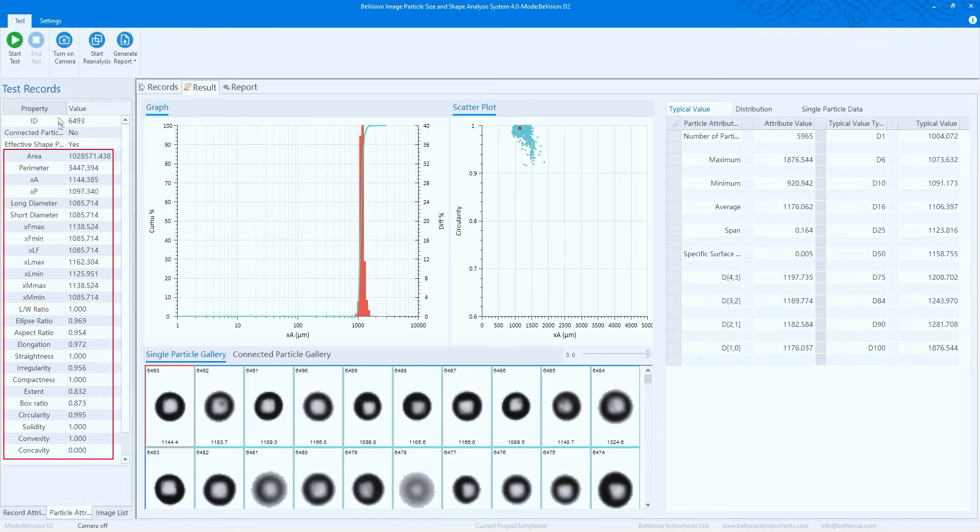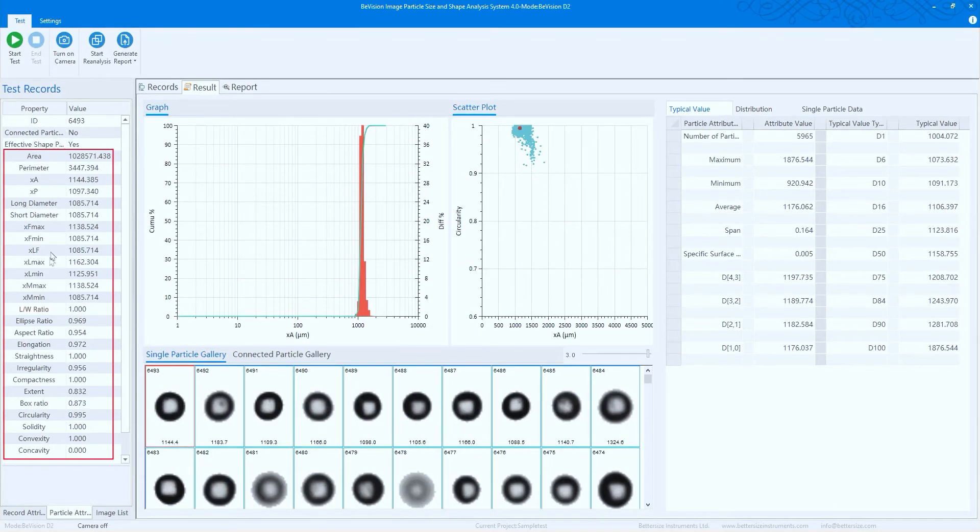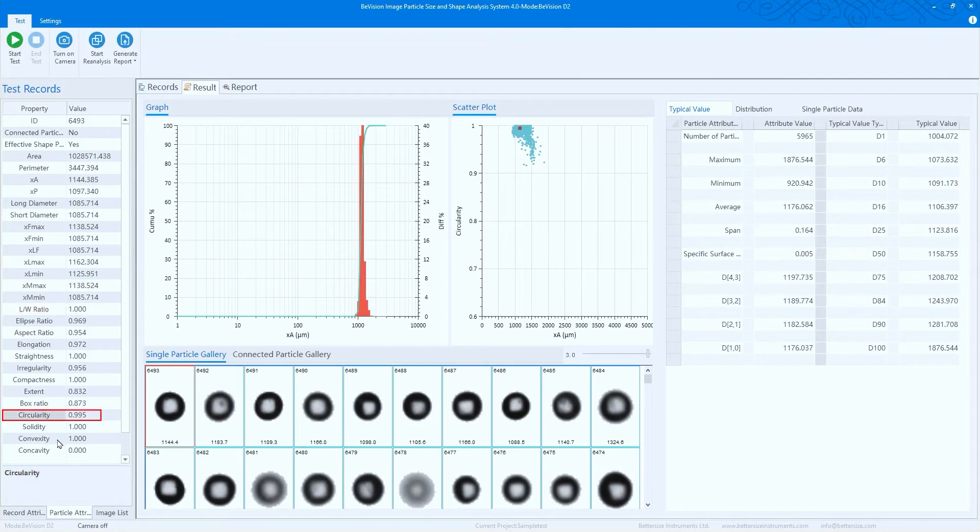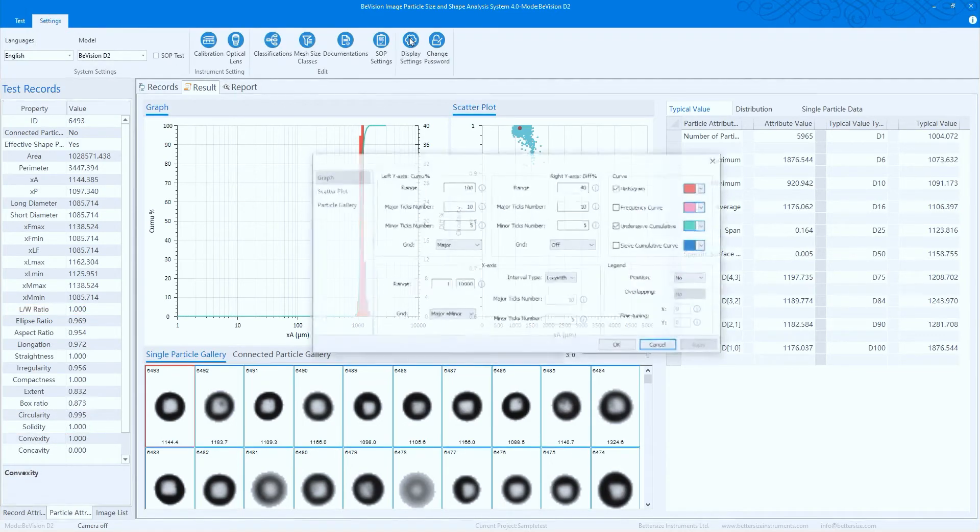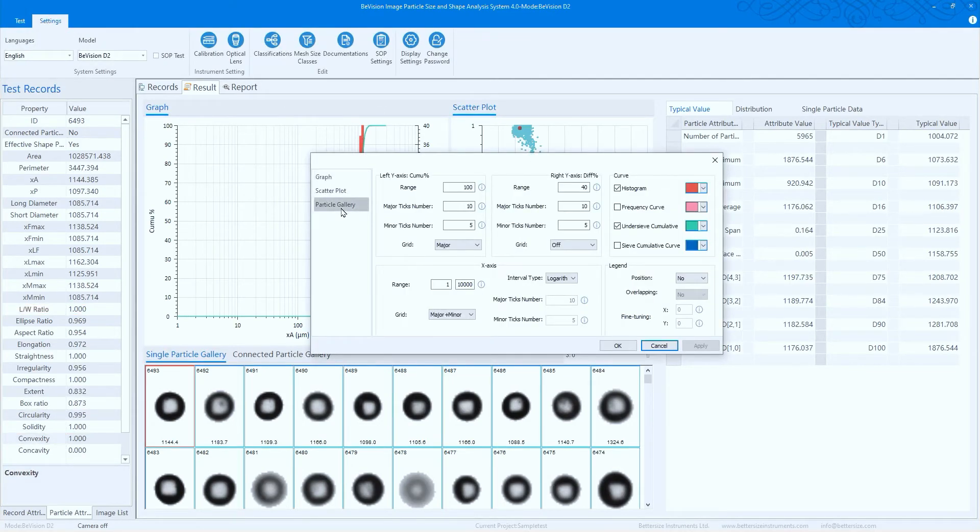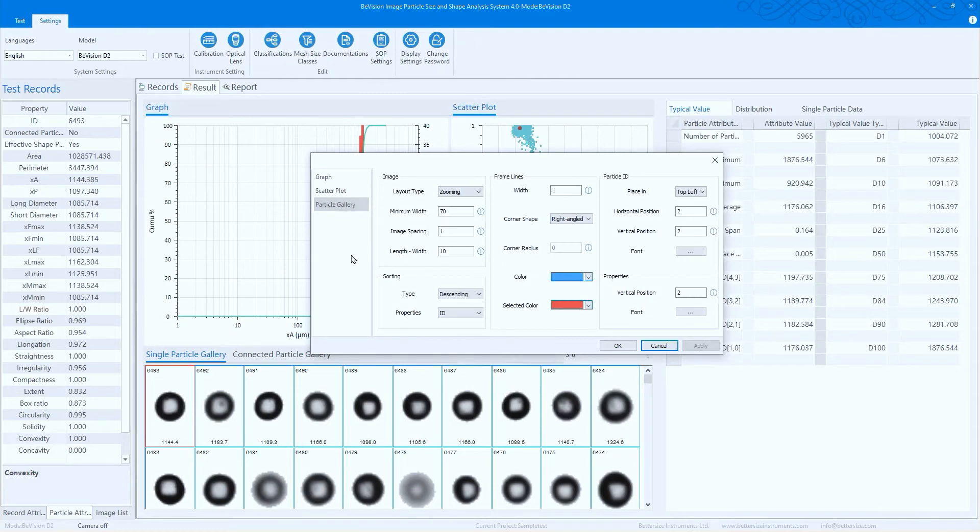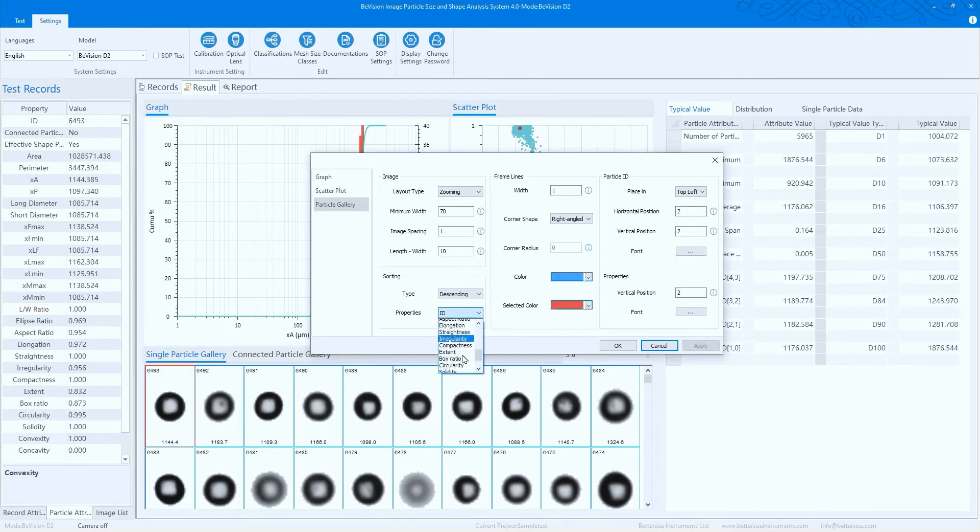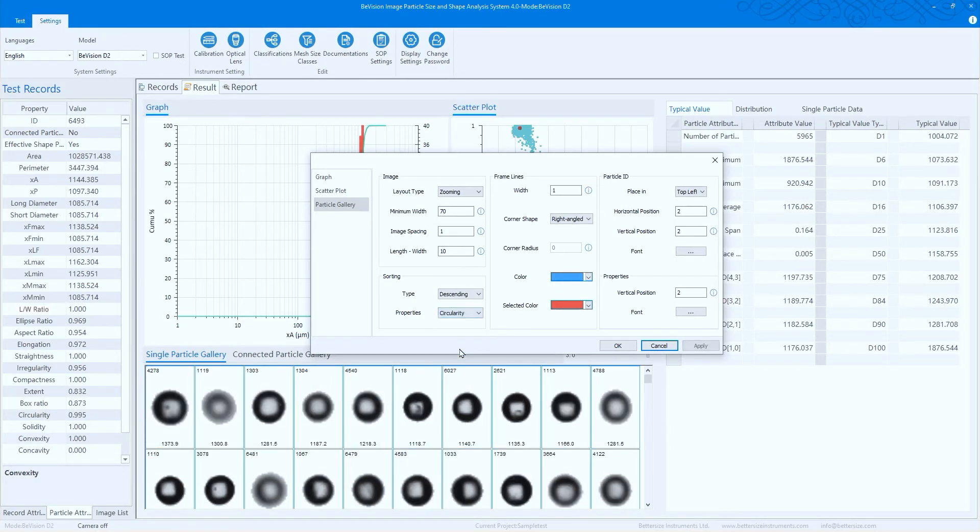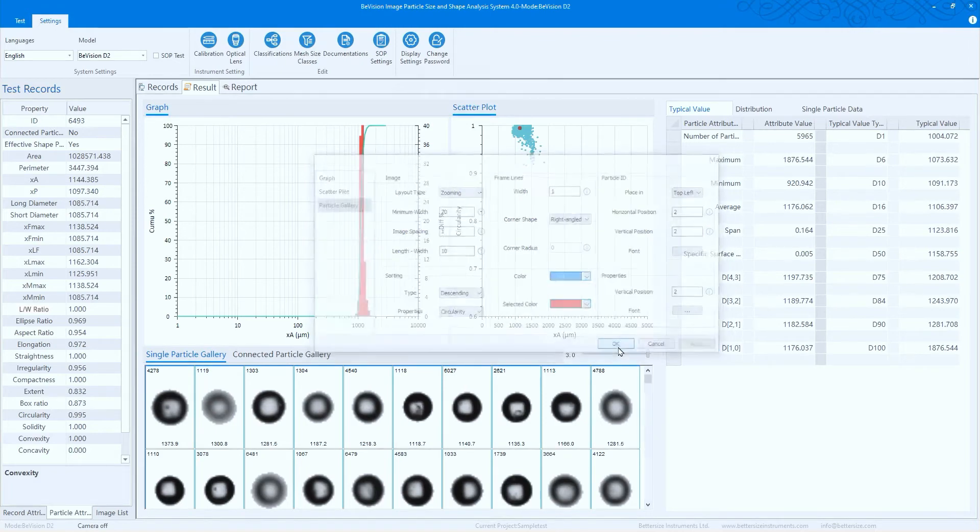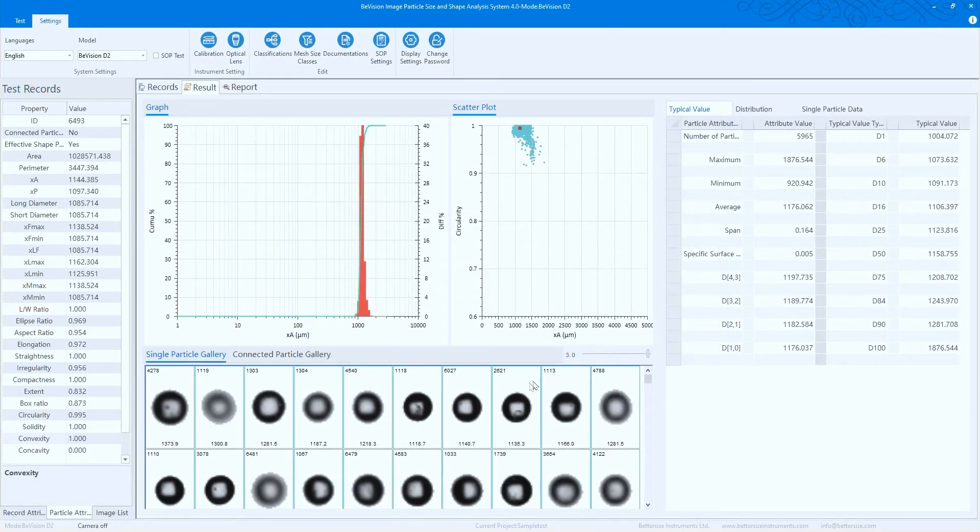Most shape parameters are in compliance with ISO 9276-6, such as aspect ratio, circularity, and convexity. In the particle gallery, all individual particle images can be viewed directly. If you are interested in any specific shape parameter, it can be sorted by circularity or by aspect ratio in the single particle data window. This enables a deeper understanding of your sample's characteristics and final product performance.